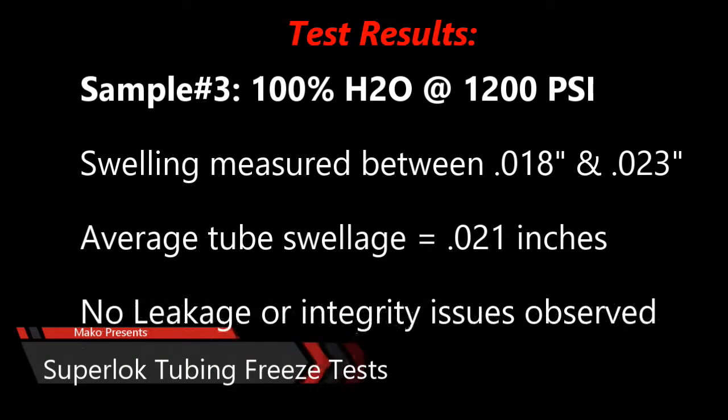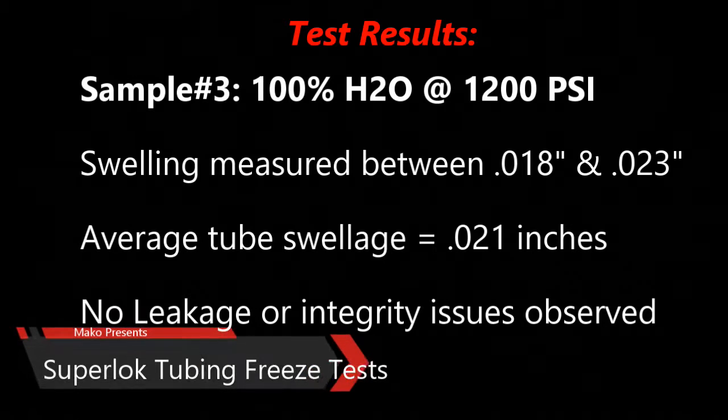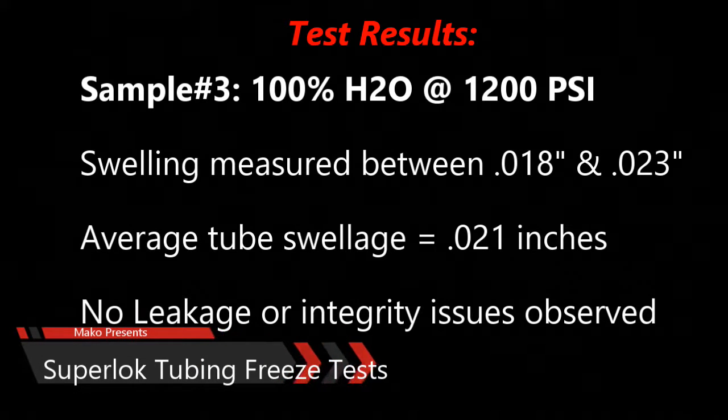Test sample number three was filled with 100 percent water and pressurized at 1,200 PSI. Recorded an average tube swellage of 0.021 inches. There was no leakage or integrity issues observed in the sample.